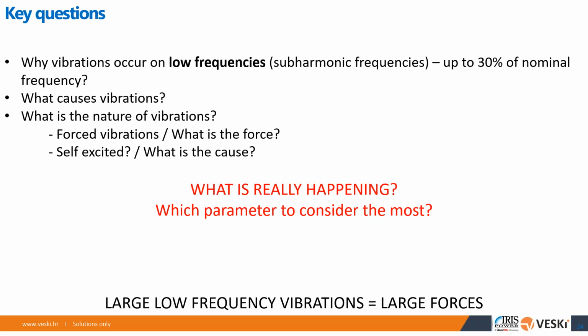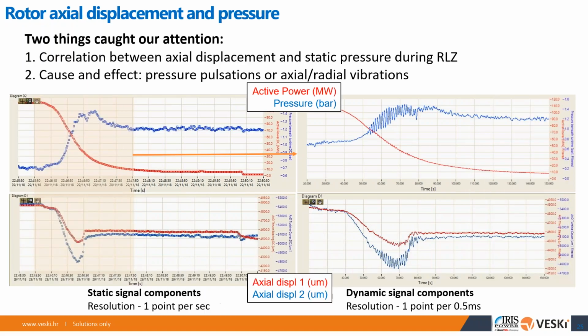It's basically self-exciting vibrations, right? So we'll be going through different parameters that we think are the key for monitoring that I mentioned in the beginning, and we'll show the graphs and how the machine behaves, right? So first, what came to our attention is that pressure, of course, but also axial position of the machine, axial lift, are correlated.